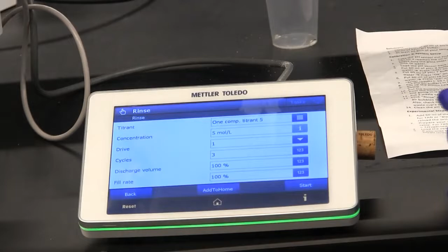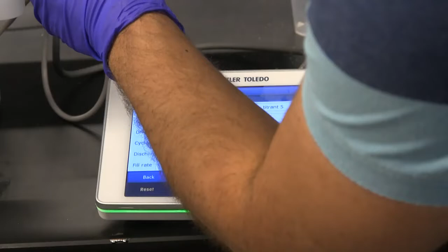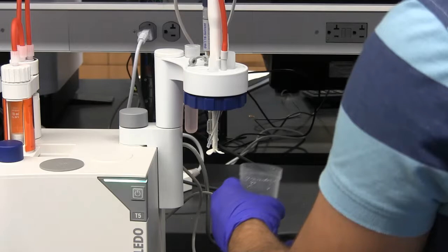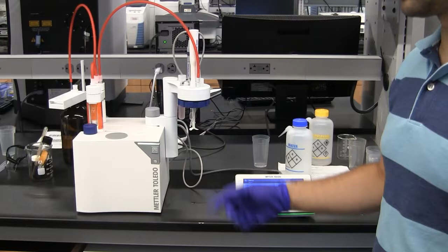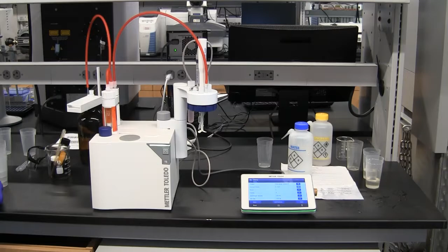So now we just need to clean this area that has been subjected to KOH with distilled water, just to make sure it is clean. So you just put a cup like that and start rinsing it properly. And never touch anything in here with Kimwipes or any type of wipes because it will destroy the pH sensor, and it's okay to leave it with a droplet of water on it. That's fine. So the next step would be the calibration.